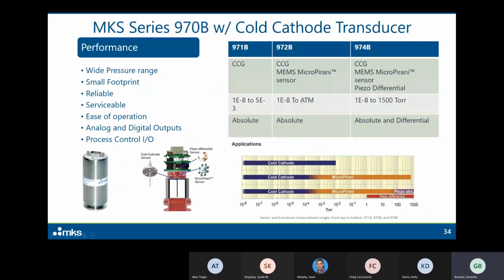So the bottom line was that with all these early successes and the surprises along the way, we were able to incorporate cold cathode gauge technology into the 900 series sensors, and this led to the MKS series 970B with cold cathode transducers. There are 3 product versions that allow us a wide pressure range, a small footprint, high reliability, and the serviceability we are looking for. The cathode gauge is a perfect example of that. It is very easy to operate: you mount it, apply some power, and look at the analog or digital output, with a lot of built-in process control I/O.